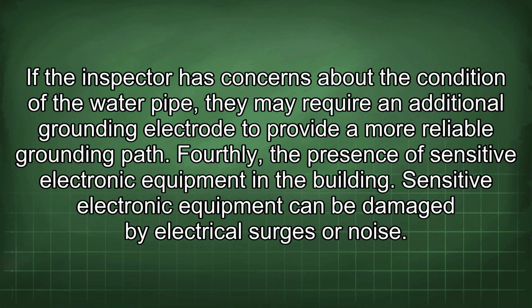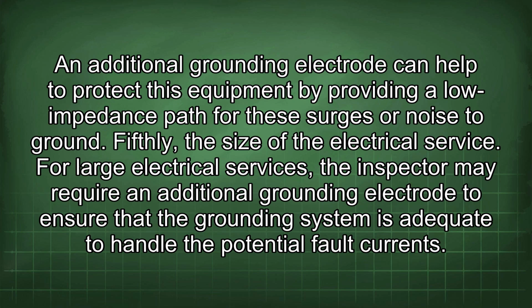Fourthly, the presence of sensitive electronic equipment in the building. Sensitive electronic equipment can be damaged by electrical surges or noise. An additional grounding electrode can help to protect this equipment by providing a low impedance path for these surges or noise to ground. Fifthly, the size of the electrical service.